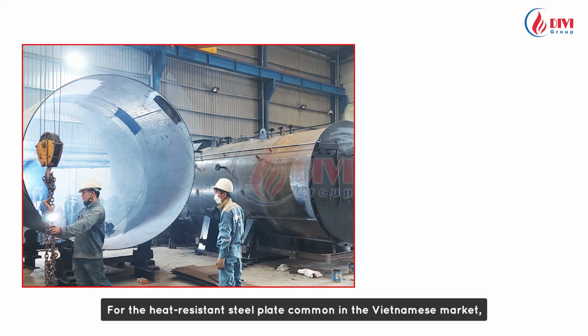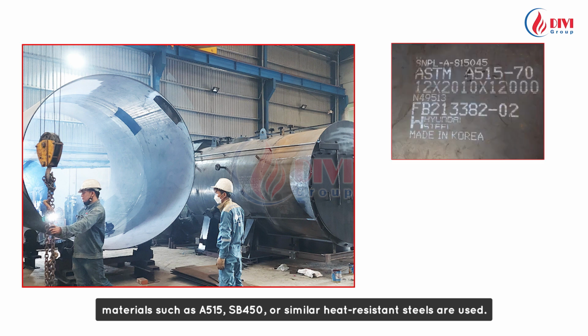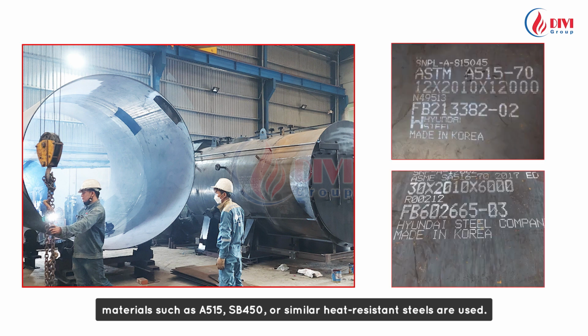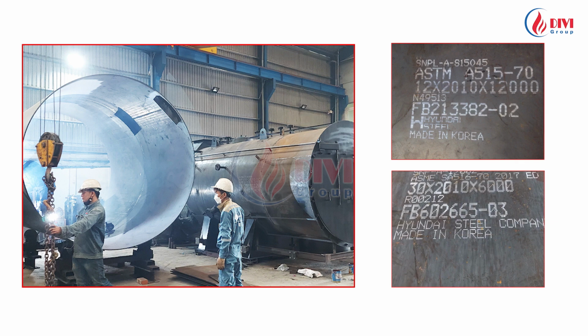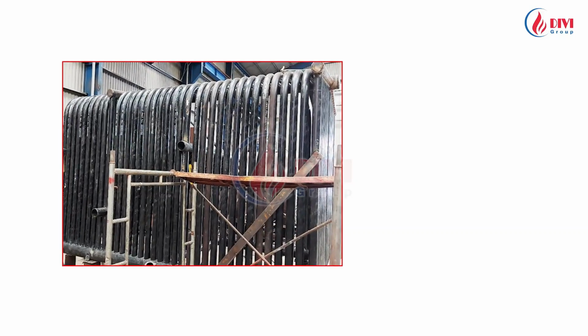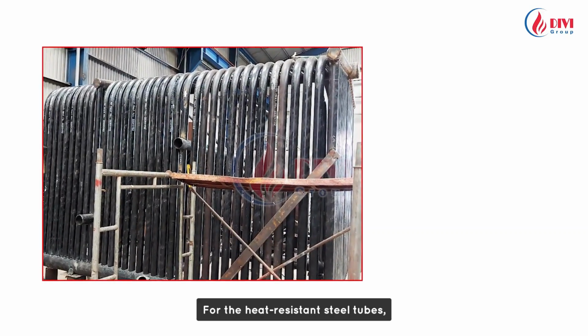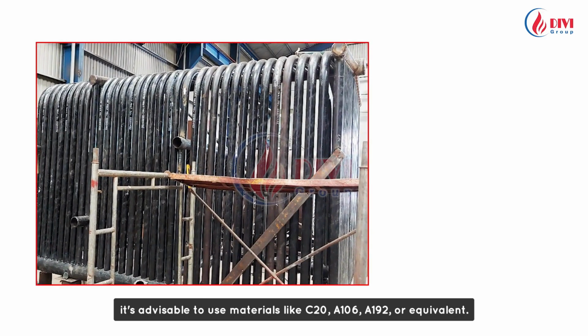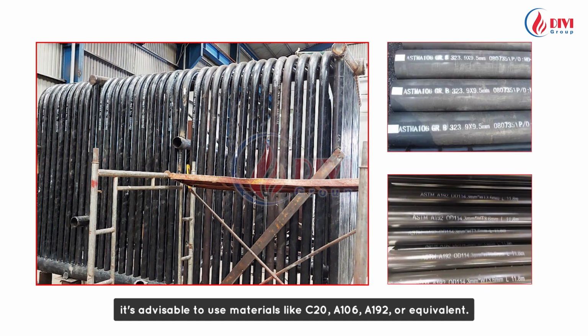For the heat-resistant steel plate common in the Vietnamese market, materials such as A515, SB450, or similar heat-resistant steels are used. It's crucial to ensure that the material chosen is indeed heat-resistant. For the heat-resistant steel tubes, it's advisable to use materials like C20, A106, A192, or equivalent.